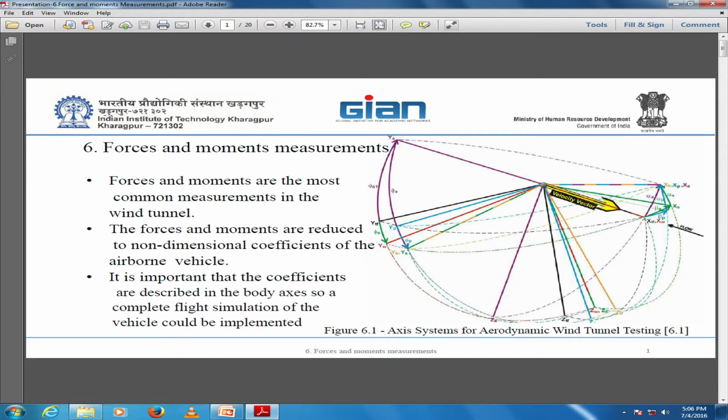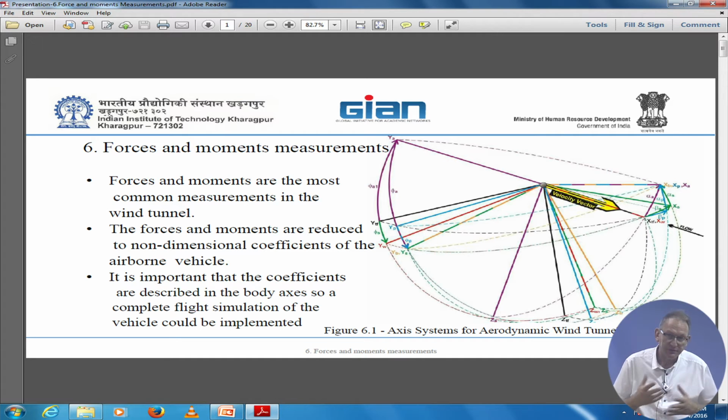We had a lot of trouble with balances that were not reliable, and this is one of the reasons the system had a very long learning curve, because it was interacting with the reliability of the balances you were given. If the balance is not reacting well, it disturbs your results. You don't know if it's coming from the calibration machine or from the balance.